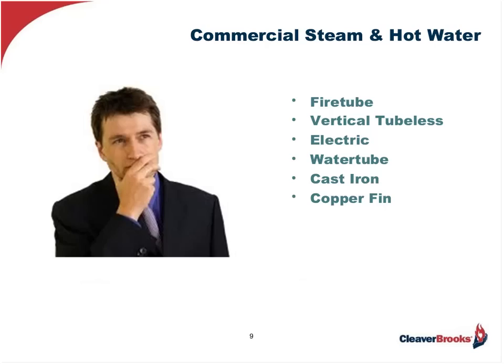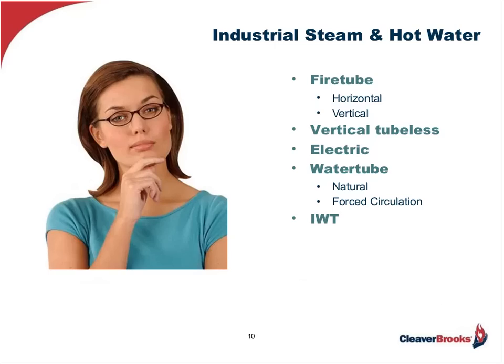In the commercial segment, needs can be satisfied with an array of boiler types including fire tubes, vertical tubeless boilers, electric boilers, water tube, cast iron, and copper fin boilers. Most will be built in accordance with Section 4 of the ASME code for low pressure. The industrial segment emphasizes process steam, with boiler types somewhat similar to commercial products, though cast iron and copper fin boilers have been eliminated due to their inability to achieve higher design pressure. In the industrial segment we have fire tube boilers both horizontal and vertical, the vertical tubeless, electric, water tube both natural and forced circulation, and large industrial water tubes — also known as IWTs.